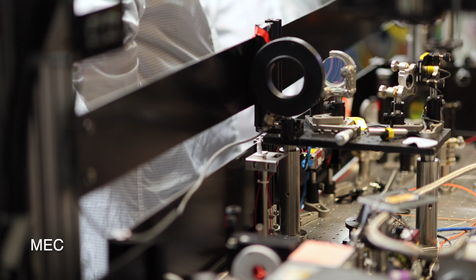Additionally, MEC's nanosecond Nd glass laser provides variable pulse shapes between 5 and 35 nanoseconds with peak powers up to 10 gigawatts and a pulse energy up to 100 joules. These pulses are primarily used for shock physics and dynamic compression experiments. MEC also offers a VISAR laser and a commercial optical parametric oscillator as optical diagnostics. Beam delivery platforms are available for focusing either the short or long pulse beam to target using rapidly installed components.